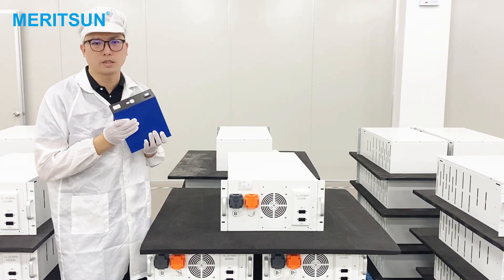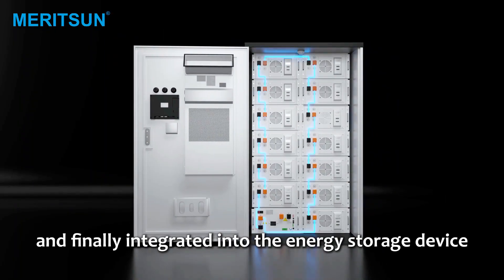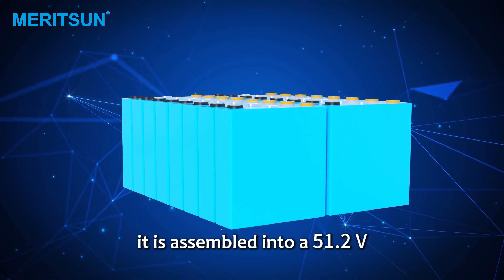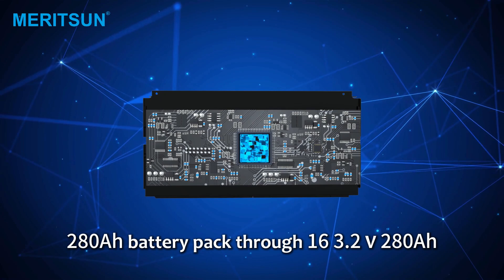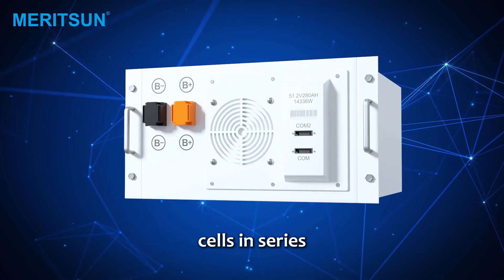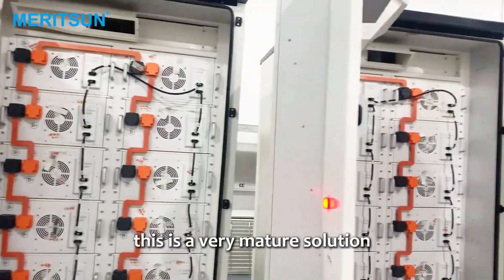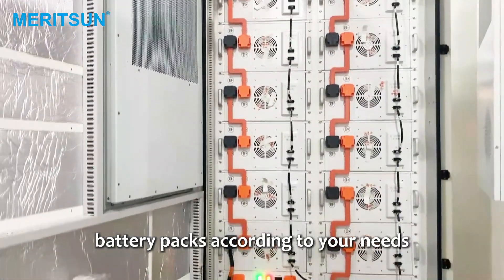With the support of BMS, the battery pack can be assembled into the entire system and finally integrated into the energy storage device. For example, MeritSun's 215-kilowatt-hour battery cabinet is assembled into a 51.2-voltage 280Ah battery pack through 16 3.2-voltage 280Ah cells in series, then connects 15 battery packs in series to form a 215-kilowatt-hour battery cabinet. This is a very mature solution. Of course, you can also freely combine more or less battery packs according to your needs.